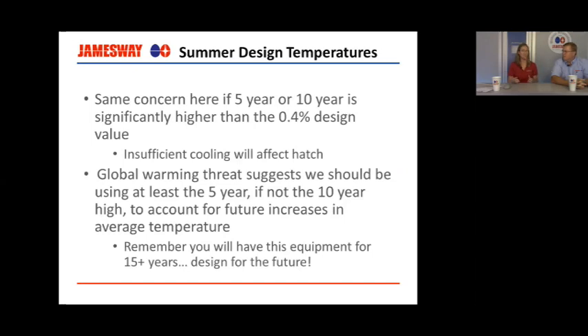And a lot of customers have actually been talking about global warming. We can't project what the temperature rise in your specific location is going to be, but I think it's a safe bet that if you're looking at your 5 year or your 10 year, and they're more than 10 degrees Fahrenheit higher than your normal design temperature, then you should consider using those. Because we do know that global warming is a fact, that there is increases in average temperature around the globe. And what you don't want to do, because this equipment should last you 15 years or more, you don't want to have to replace it or augment it because of poor design in the beginning.